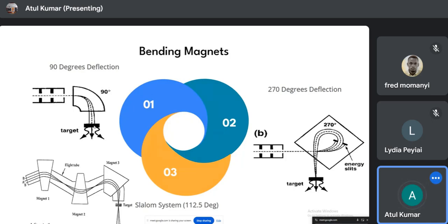So they do not create a very nice focus. The diameter of that focus will be very high in this case, and you will not have very sharp X-ray images or very sharp X-ray production, because of the penumbra effect and all those things. We want it to be very sharp. That is why scientists have designed another, the 270-degree bending magnet, in which the same effect happens but it kind of negates itself, and then you have a very sharp bending using 270 degrees.